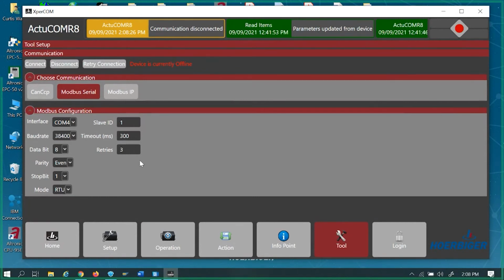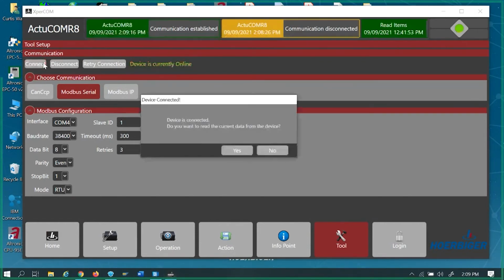If somebody's communicating with this, you probably need to get their slave ID. There is a way to get it through the reset function, but I think it'd be easier just to ask them to give you that slave ID number, especially if you want to get onto it. So I'm going to connect to it. Typically it says device is currently online, and it asks if I want to read the data that's on it. I always hit yes on this.